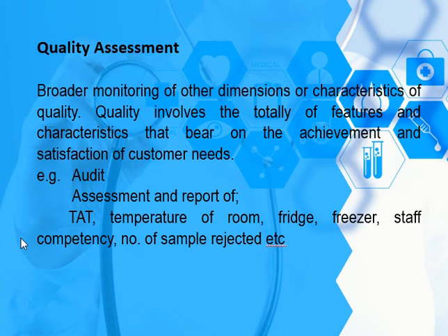So for quality assessment, it is a broader monitoring of other dimensions or characteristics of quality, and quality involves the totality of features and characteristics that bear on the achievement and satisfaction of customer need. So quality assessment could include audit, the assessment and report of turnaround time, temperature of room, fridge, freezer, staff competency, and number of samples rejected, etc. Meaning that quality assessment is the activity of assessing the workflow performance from time to time or at interval time.